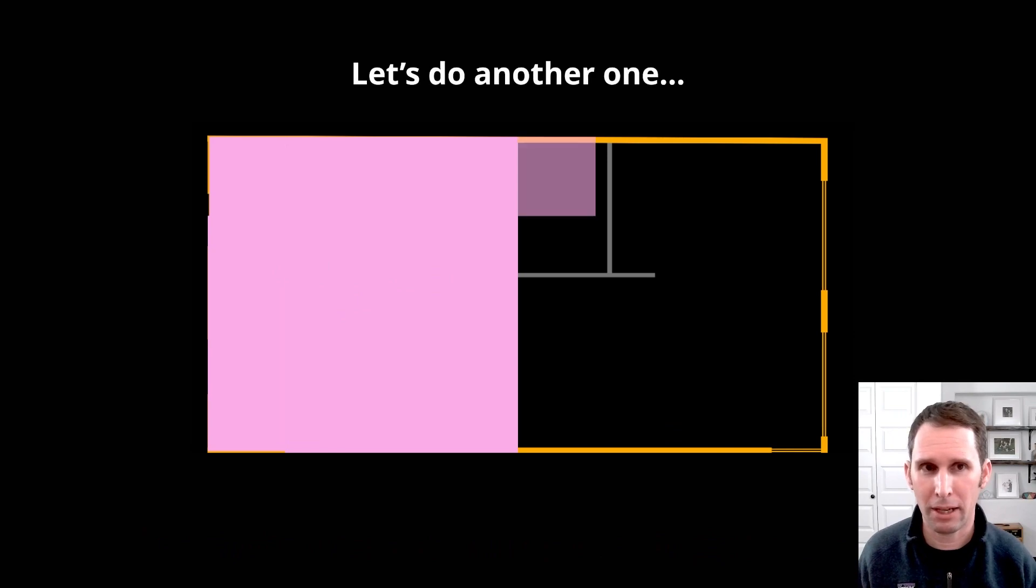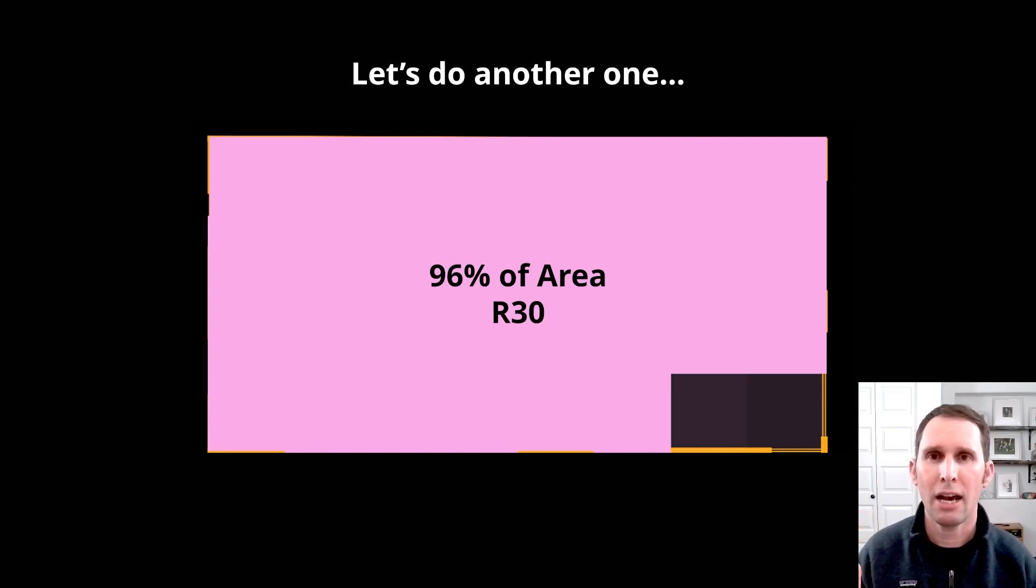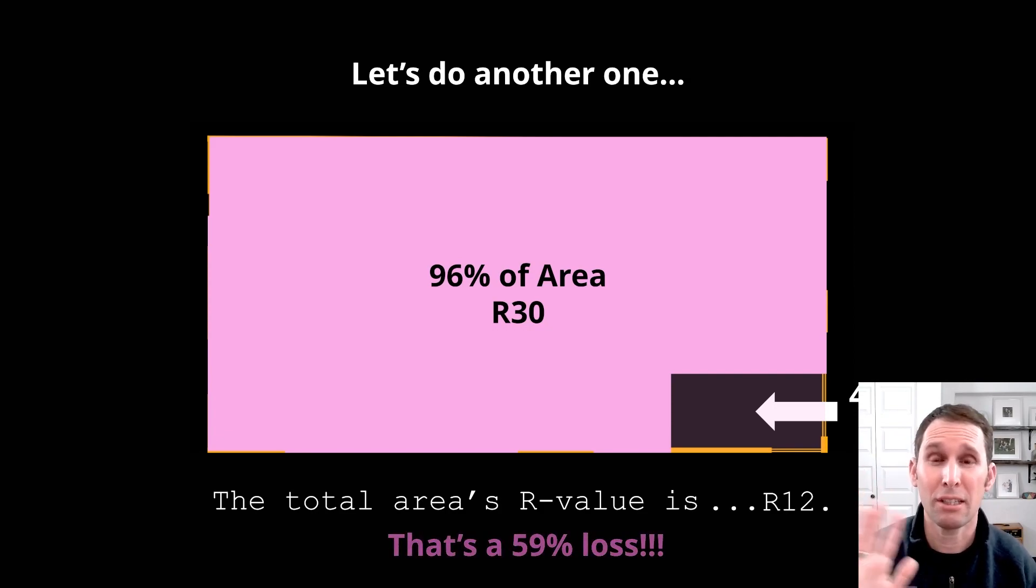Let's do another one. It'll make more and more sense as you look at more examples. So, imagine you have an attic that has 96% of the area of R30 and only 4% of the area having R1. What do you think the total average is? Well, some people would say, oh, well, you're probably losing 4%. Maybe it goes down to R25. In this case, the total area's R-value is only R12. That's a 60%, almost a 60% loss. So, again, heat travels the path of least resistance.